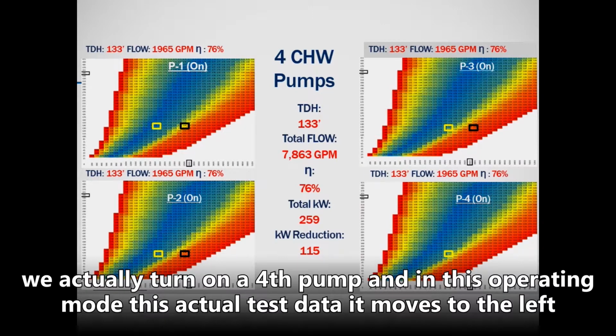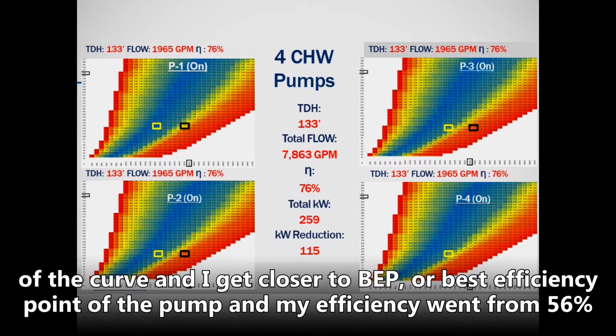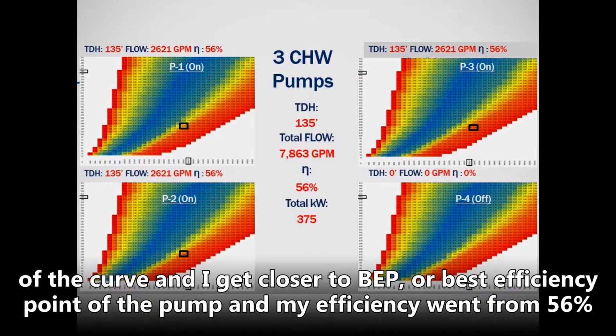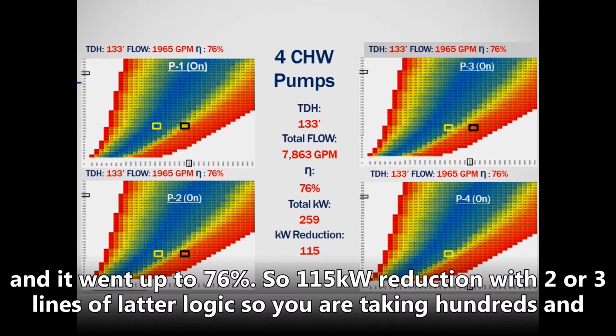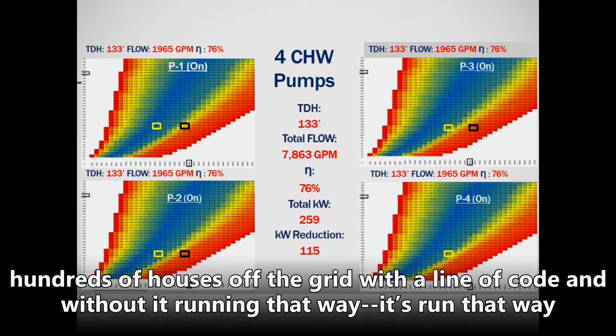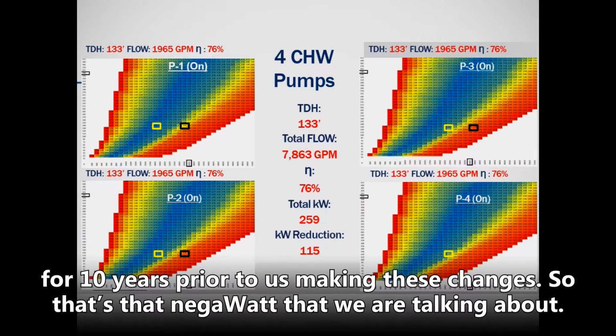This is actual test data. It moves to the left of the curve, and I get closer to what's called BEP, or best efficiency point of the pump. And my efficiency went from 56 up to 76. So 115 kW reduction with 2 or 3 lines of ladder logic. And so you're taking hundreds and hundreds of houses off the grid with a line of code, and it ran that way for 10 years prior to us making these changes. So that's that negawatt that we're talking about.